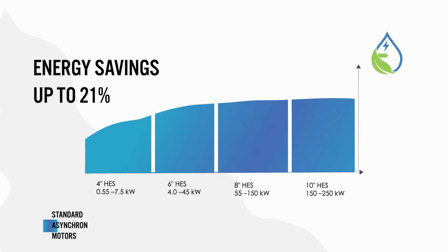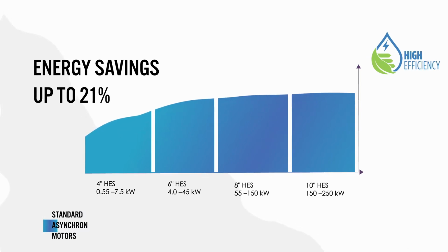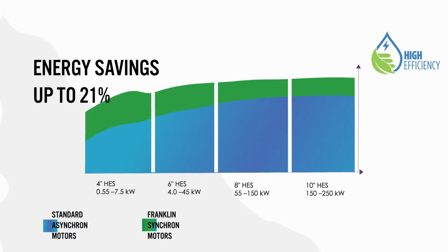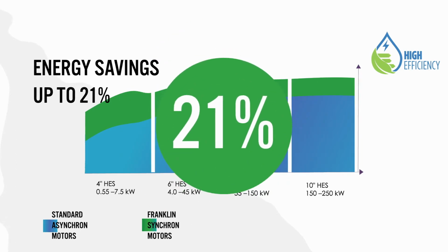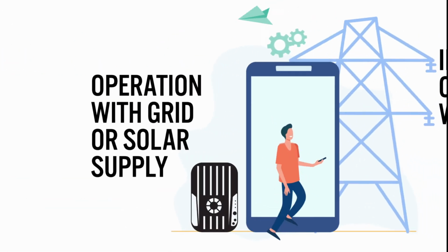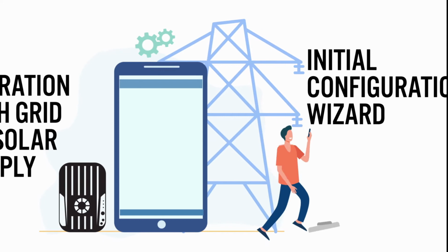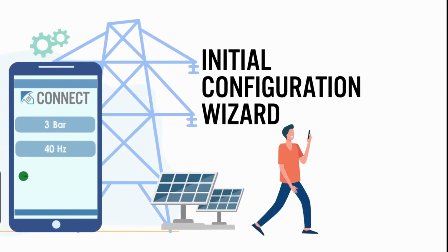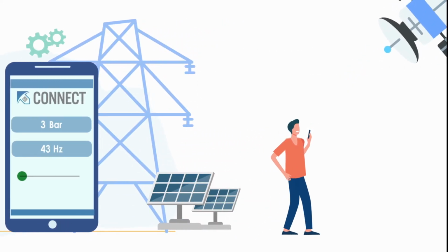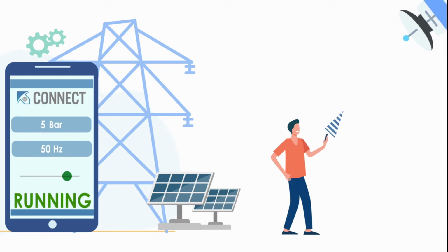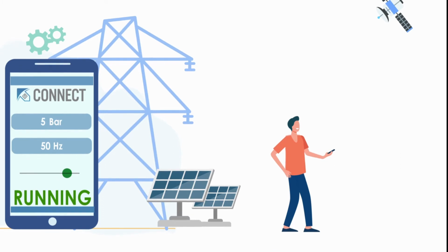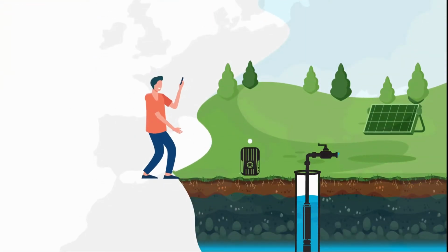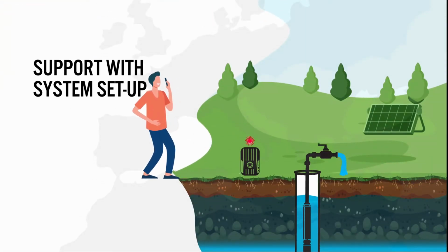These are the efficiencies of standard asynchronous motors. These are the efficiencies of Franklin PM motors. So outstanding improvements up to 21% of efficiency can be achieved over the whole range. For the operation of a PM motor, a frequency converter is required, which once again significantly improves the efficiency. Franklin Electric offers various models that are suitable for grid or solar supply. A setup wizard guides step by step through the drive settings, making setup easy.